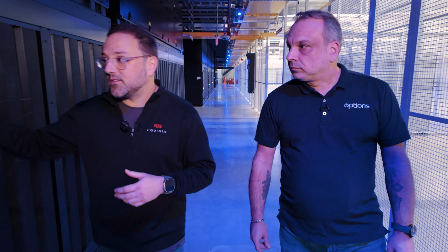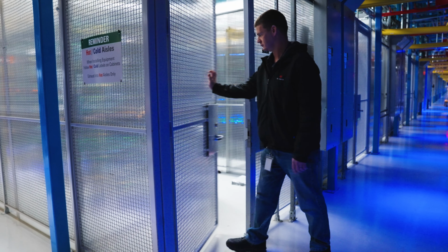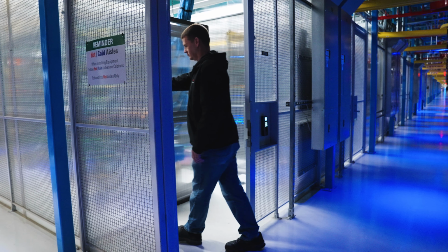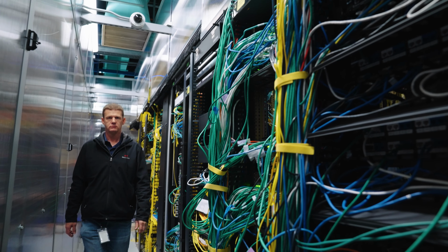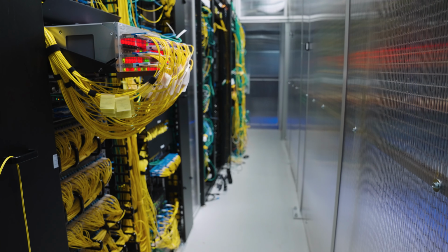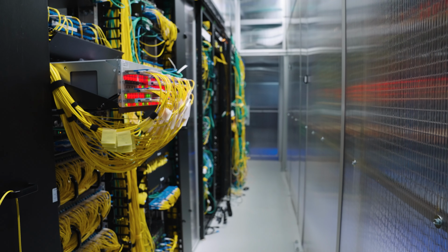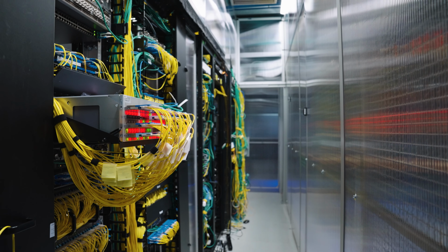Another difference in design between NY3 and NY4 is the hot aisle versus cool aisle approach. At NY4, it's a cool aisle design where cool air floods right over the cabinets. At NY3, we have air handler units pushing cold air to flood the entire area, with hot aisle containment right above the cabinets that sucks the hot air up above the ceiling, circulates it, cools it again through the air handling units, and pushes it back into the space. That's a much more efficient design.